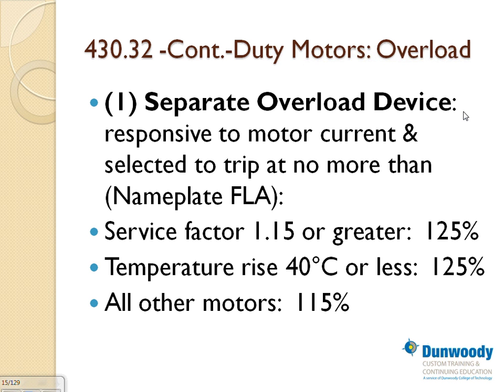So if something jams this motor, before it starts smoking, if you don't have an overload and you jam a motor, the circuit breaker will wake up and trip eventually. But by that time, smoke will be there and probably fire will be engulfing the whole motor. So yeah, great, your circuit breaker woke up, but we lost a 100 horsepower motor. Now you have to go buy a new one. So that's why the smart people decided to put the overload protection on almost all equipment that has motors.